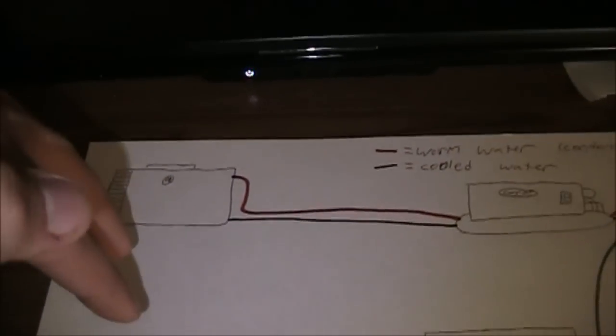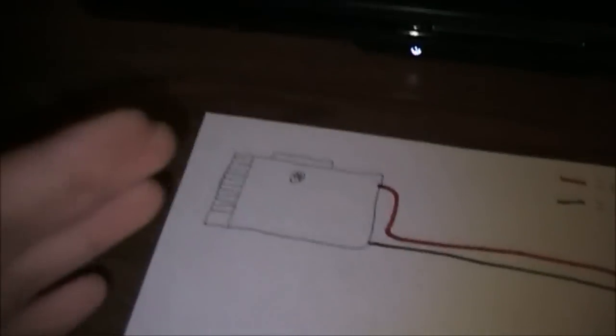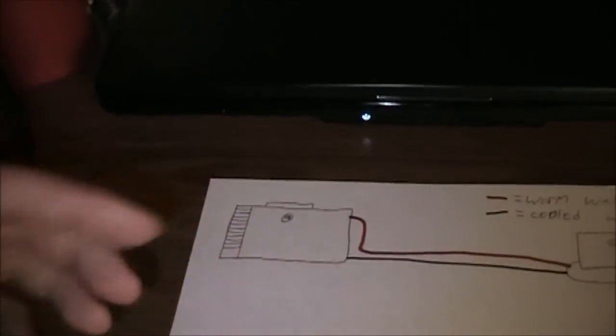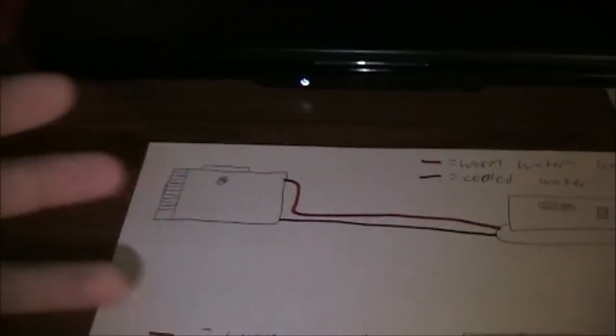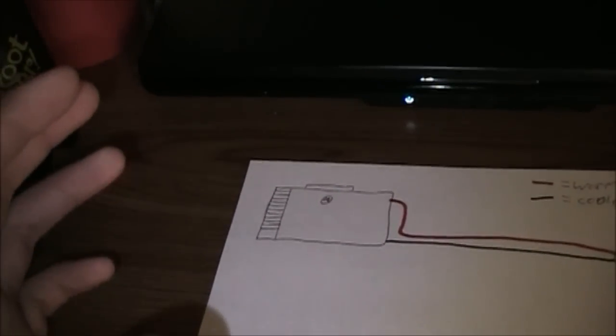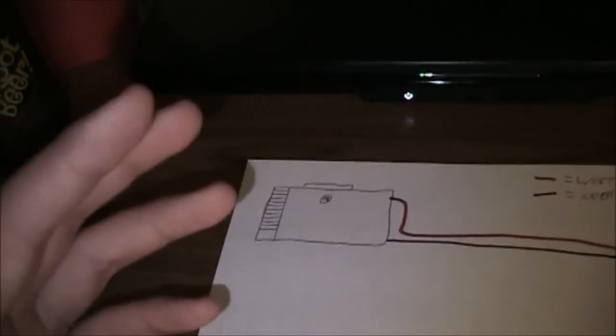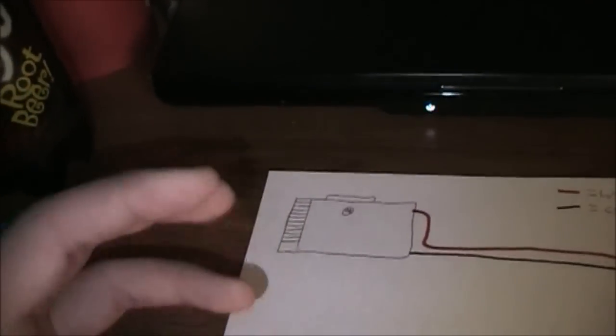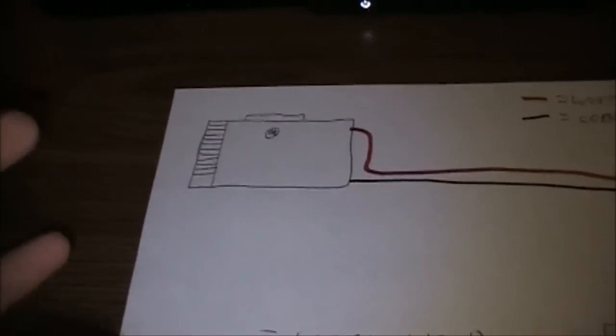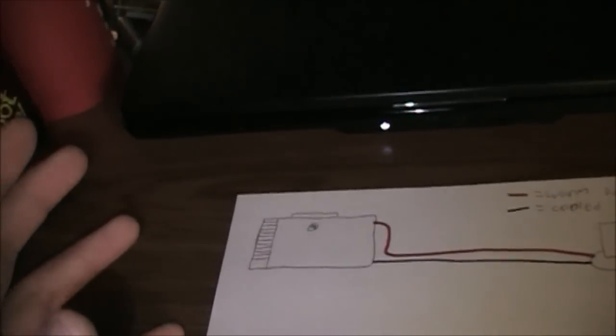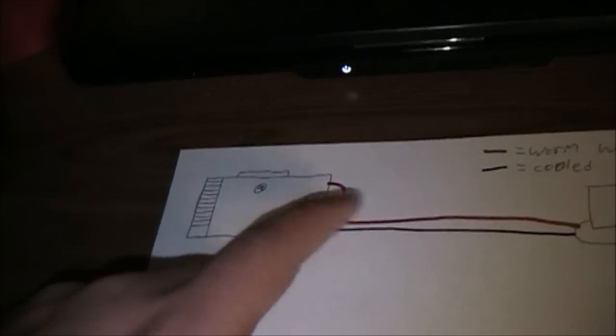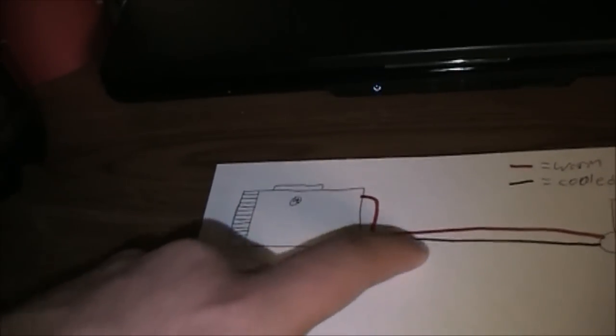And there it trickles down through the media, and a very powerful fan sort of wicks the air up through the media, evaporating some of the water. And since it evaporates some of the water, that evaporation cools the remaining water down below the outside ambient temperature. So even if it's 100 degrees outside, it's cooling that water down to about 77-78 degrees Fahrenheit.